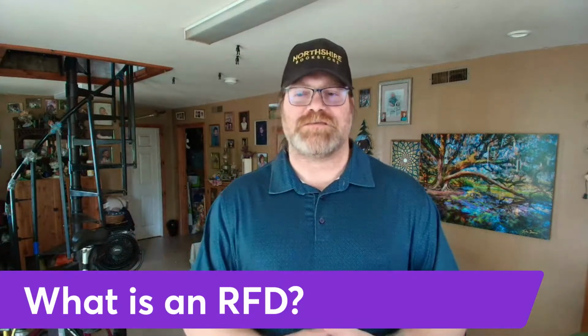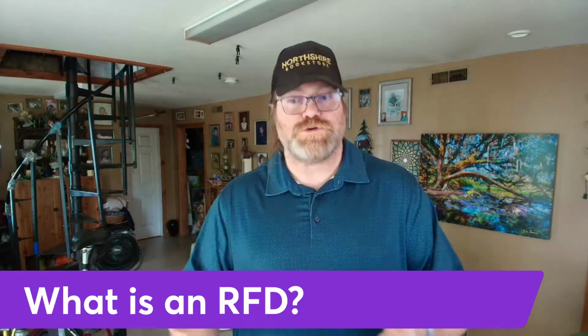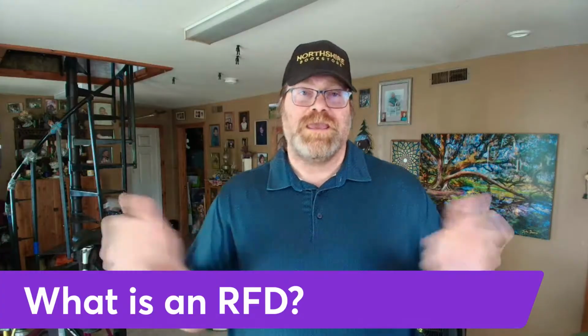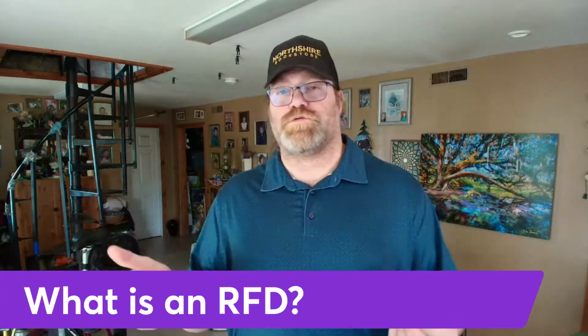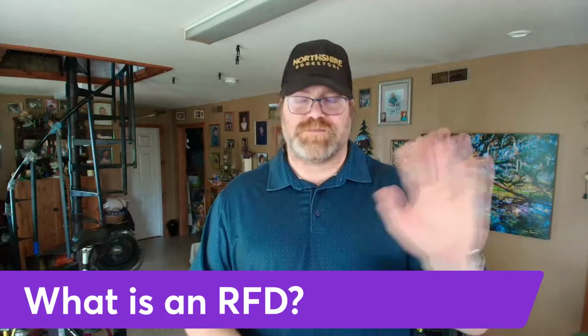Do you have an existing pre-RFD? So that's what you would do. You'd submit a pre-RFD to the Office of Combination Products and say, is this a combination product? We don't think it is. Here's why we don't think that. Do you agree with this? Get it in writing. You're done. Not a combination product. Keep on going.